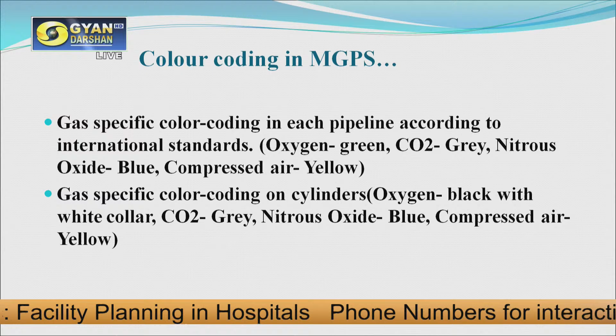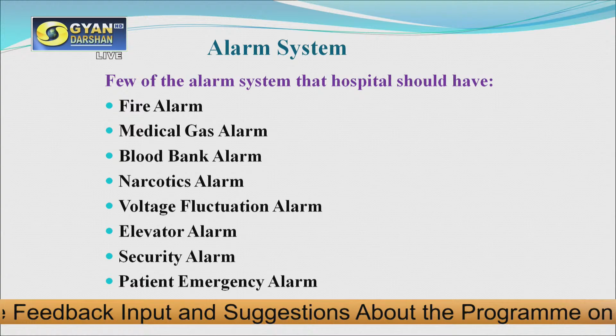This is the typical color coding. Color coding is gas specific. Oxygen is black with white, carbon dioxide is gray, nitrous oxide is blue, compressed air is yellow. Alarm system, I think we have spent enough. The alarm system would be detecting fire, the medical gas pipeline system, and blood bank alarm. The blood bank alarm monitors the temperature, which goes on circulating.